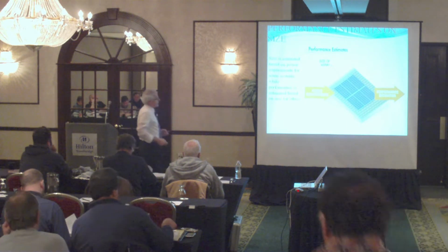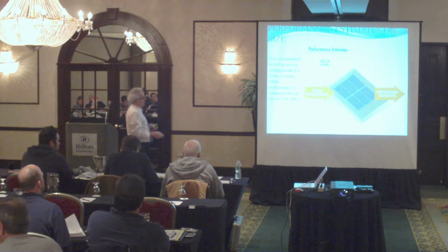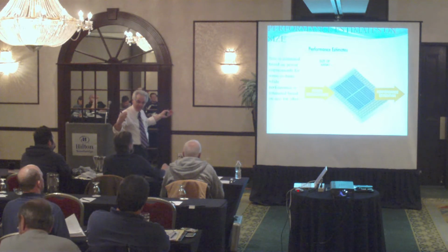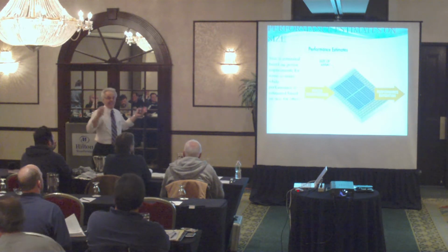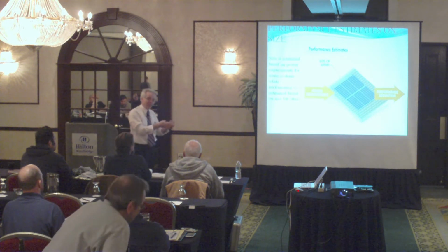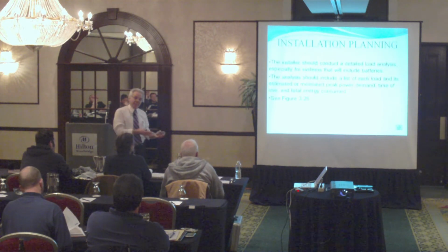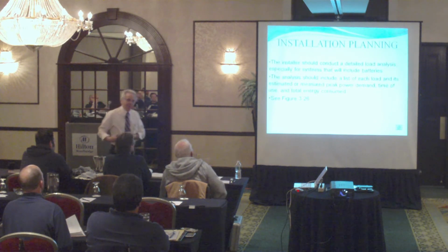Okay. Sometimes the performance is based on what? On power requirements. Sometimes it's based on what? On size requirements. What do we mean by this? You say to the guy, okay, we're going to get so much power out of the system, or I'll install your system for a particular size. Power is, I'm going to get so many kWs out, or I'm going to install your system at 5. There's a big difference between telling you I'm going to get 5 kW out, or I'm going to install you a 5 kW system. There's a big difference for that. So you got to explain that. One is performance, one is size. Because you can have a 5 kW system and only get 3 kW out of it, okay?